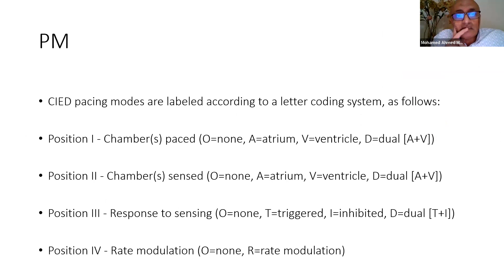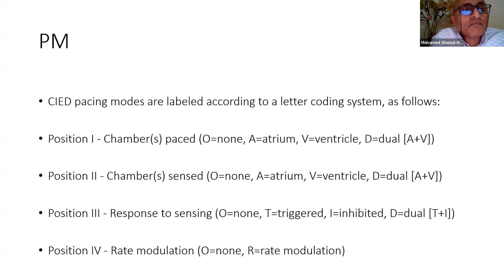The first letter denotes the chamber of the heart that is paced. The second letter denotes the chamber of the heart that is sensed by the pacemaker. And the third letter refers to the response of the pacemaker to sensing the electrical activity of the heart. The pacemaker can respond either by inhibition of pacing or by stimulating pacing of the heart after it senses the electrical activity of the heart.